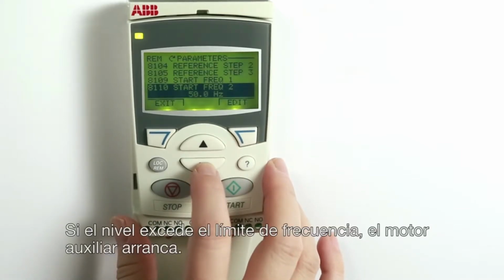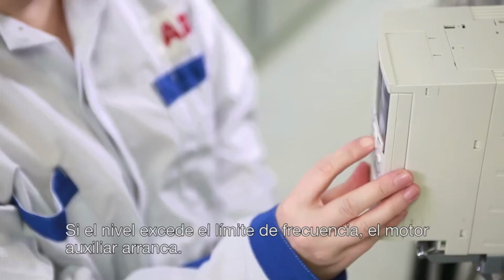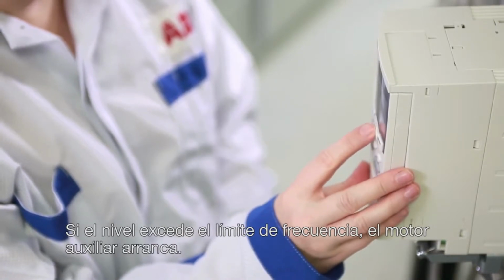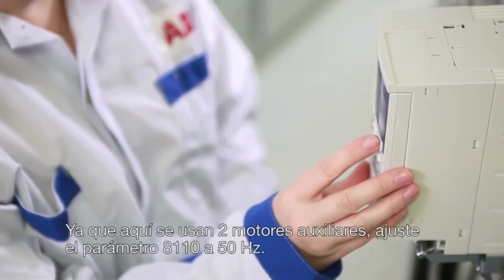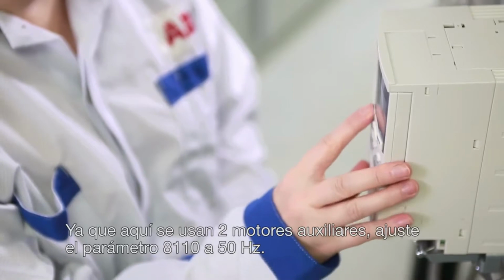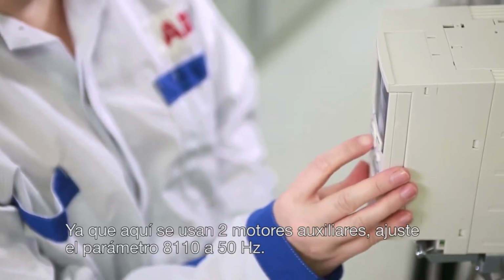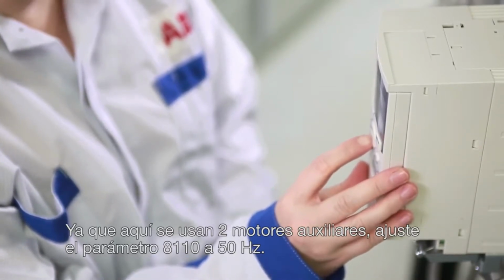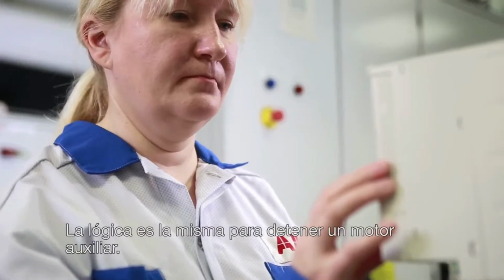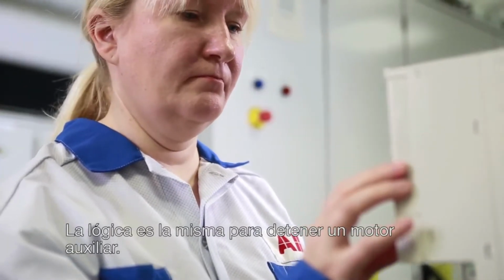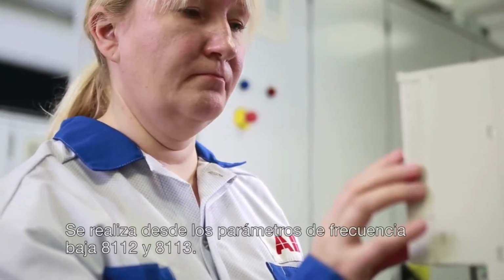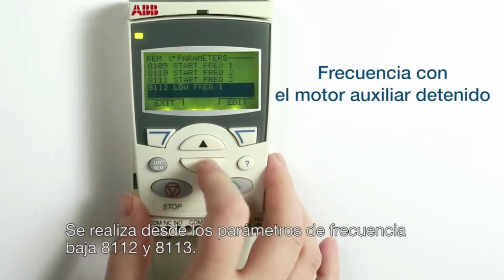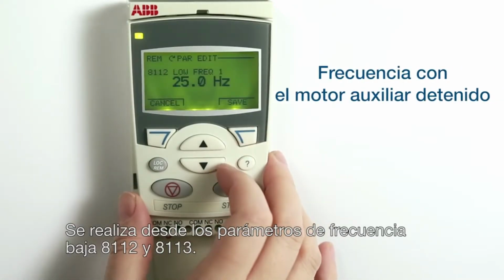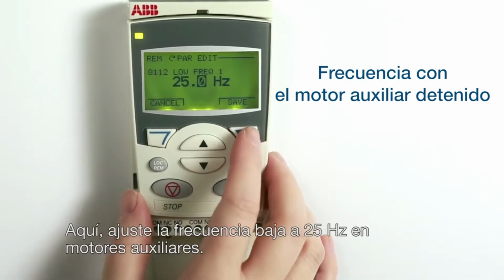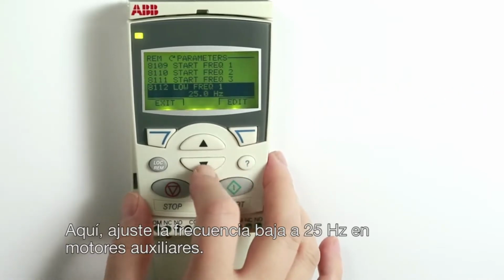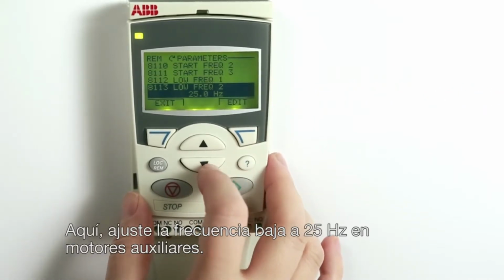When the capacity need rises above the set frequency limit, the auxiliary motor is started. Since in this exercise we use 2 auxiliary motors, set parameter 8110 also to 50 Hz. The logic is the same for stopping an auxiliary motor. This is done from low frequency parameters 8112 and 8113. In this exercise we set the low frequency to 25 Hz for auxiliary motors.